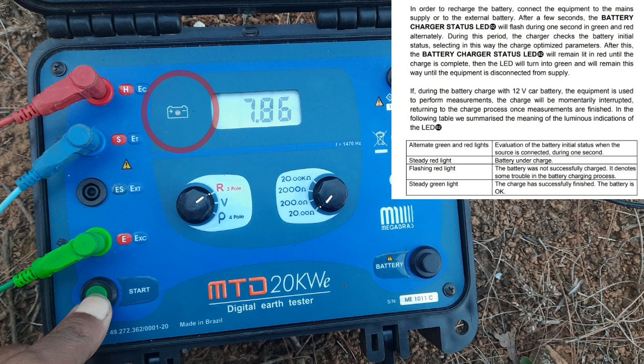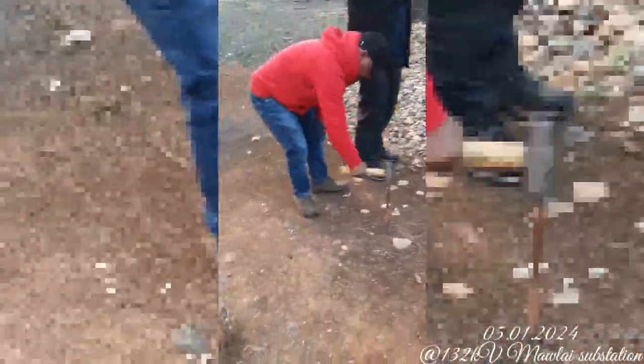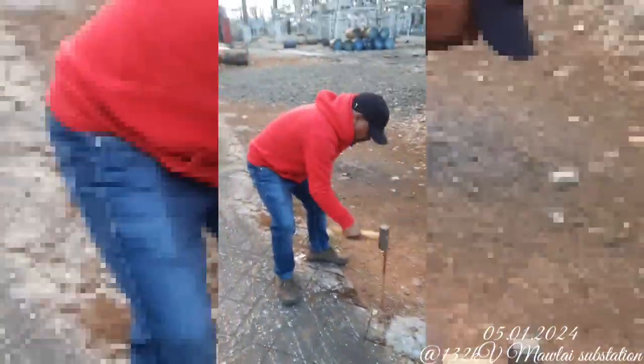Now, when doing the testing, sometimes when we insert the electrode, you will experience an acoustic alarm or beeping. This indicates the connection has not been done properly. In our case, like it happened at some of the substations, we did not insert the electrode properly. So I hammered it in properly, used a file to clean the earthing surface, connected it properly, and then the sound stopped.